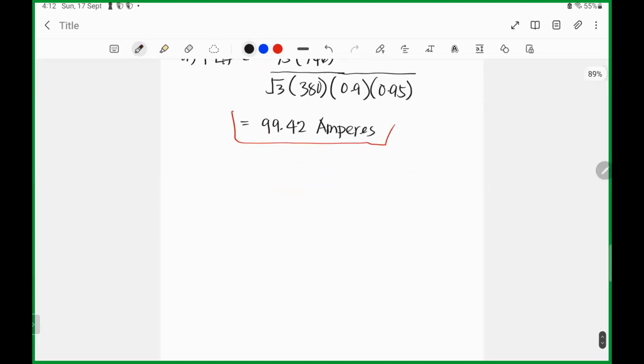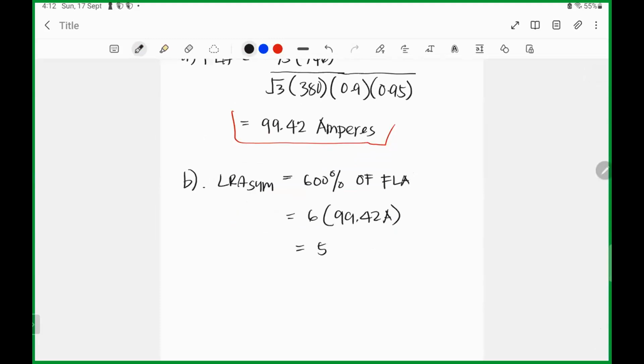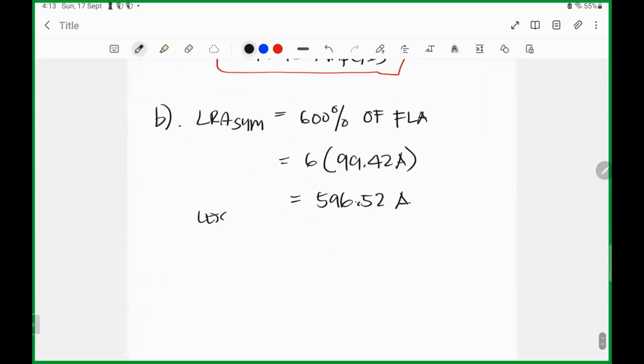Next, sa plotting, kailangan natin ng locked rotor symmetrical. So that is B. So LRA symmetrical is, sabi niya, 600% of FLA. So this one is 6 times 99.42 amps, 596.52 amps. So this one, assume natin na mag-accelerate yung motor. Let's assume na yung time to accelerate is around 5 seconds.